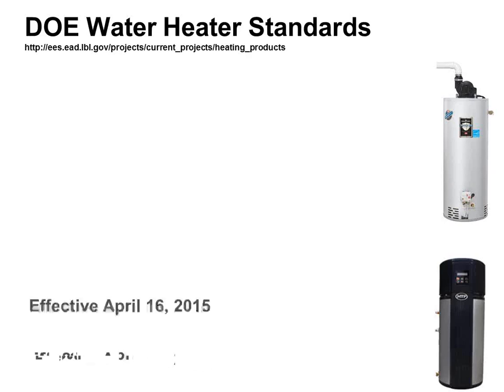Right now, our fuel costs are a little bit lower in the Midwest, so some of these numbers would change on the actual gas one, but it still gives you an idea of what it's kind of like. The way a heat pump water heater works is the same way any other heat pump works. Basically, there's an evaporator and there's a condenser, right? In this case, I'm taking air out of your building or out of your house and running that through my heat pump, and I'm stealing the heat from your house to heat my water, right?